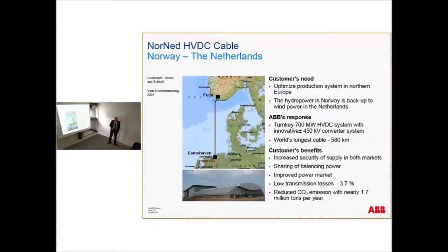The longest cable could be interesting, since sooner or later Iceland might be connected to Europe through a DC cable. The longest cable today is a cable between Norway and Netherlands. It's a 700 megawatt cable with a plus minus 450 kV system. It's 580 kilometers long, and the distance from Iceland to UK is almost double, 1200 kilometers. But for HVDC, that's not a problem from a technical point of view, since we are only looking at the resistance of the cable. We can easily transmit over 1200 kilometers. It's more a matter of the cost of the cable.